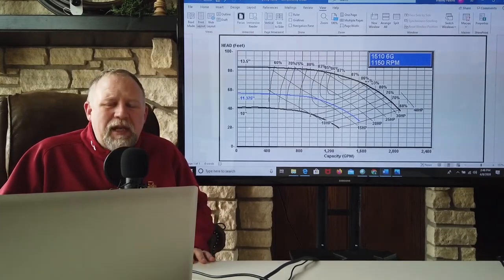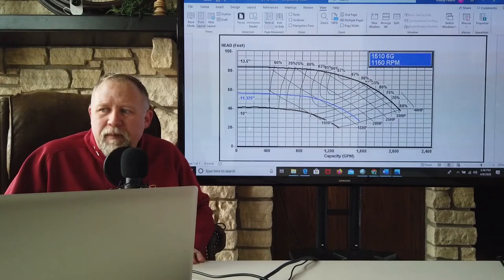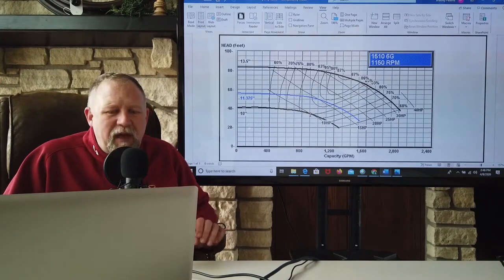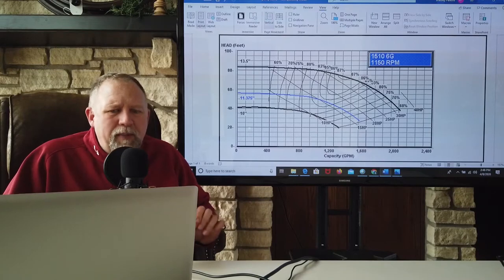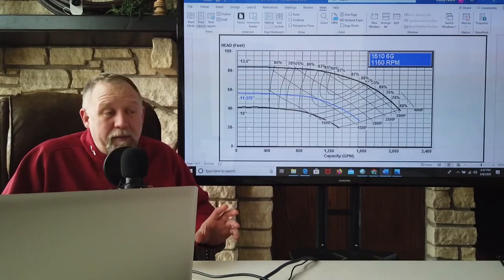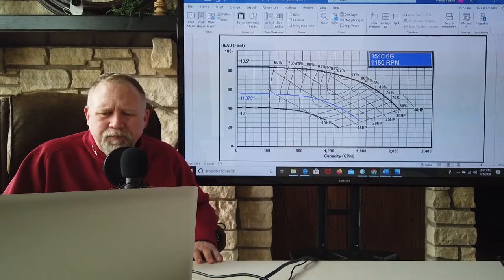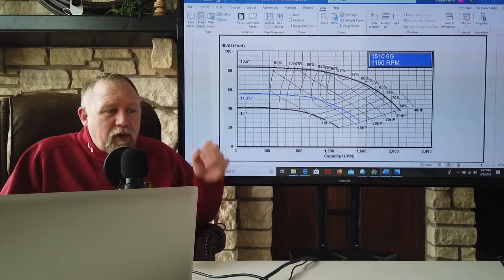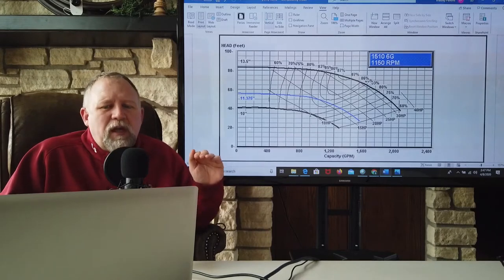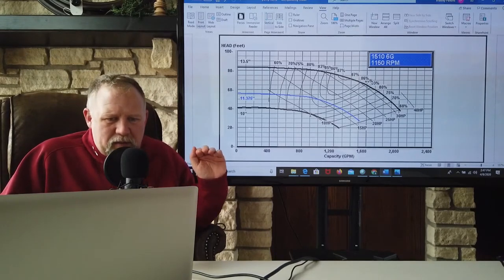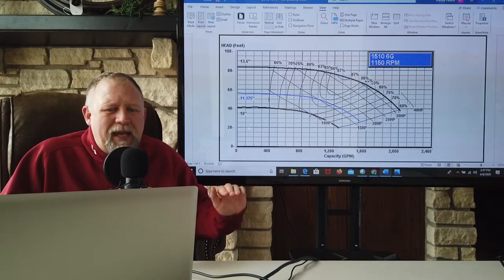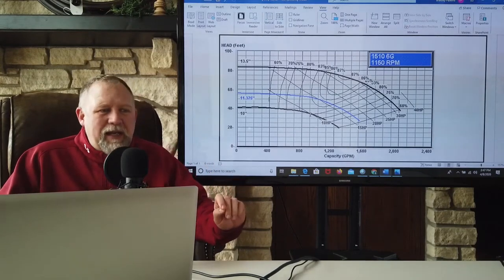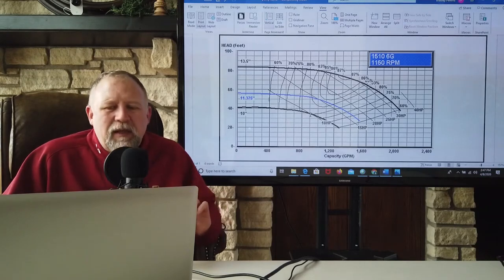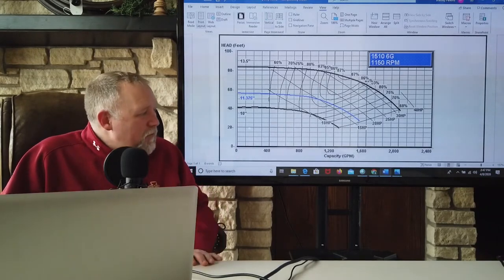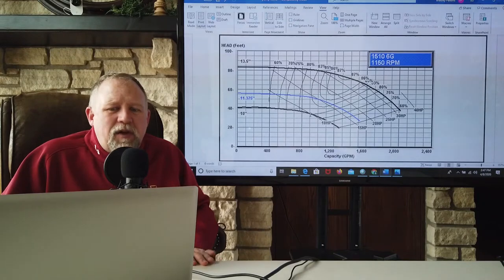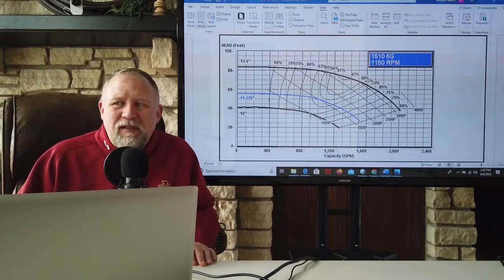When a mechanical engineer picks a pump, they are usually doing it in the design phase, well before the pumping system is actually laid out and well before it's actually put into the building. In other words, from your fluids classes, you know that the total hydraulic resistance to flow, in other words, the pump head, is an unknown. You are calculating it, but that's an estimate, really. It's not a guarantee. Many times, designers are going to overestimate the resistance to flow.